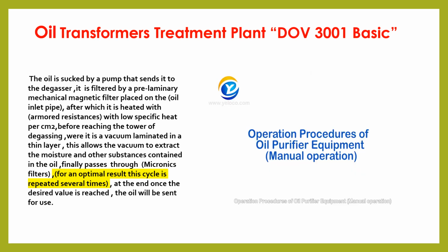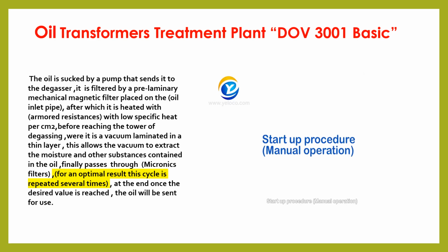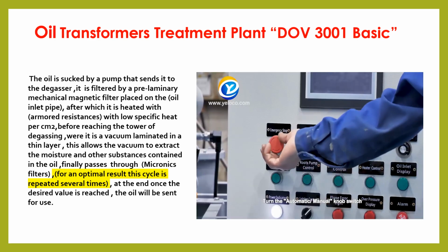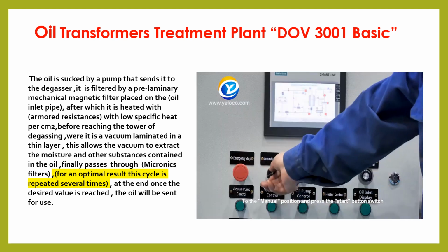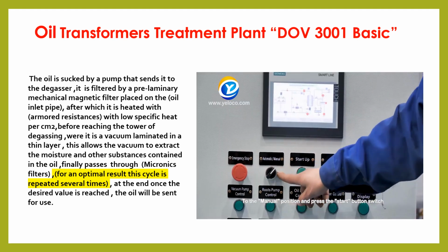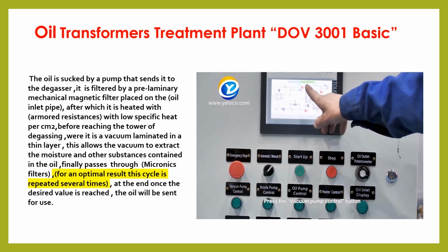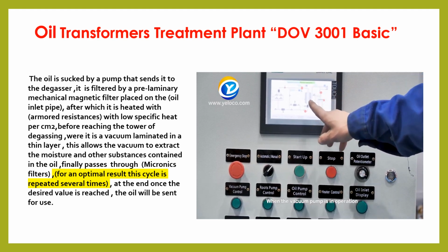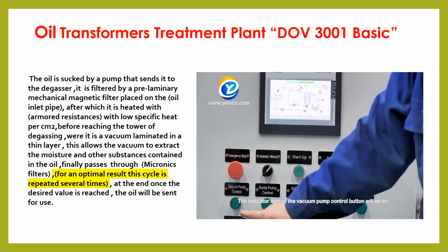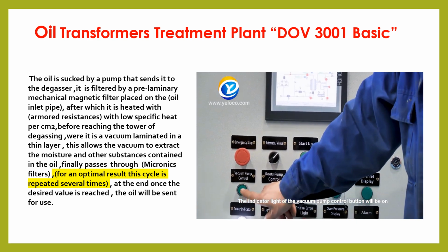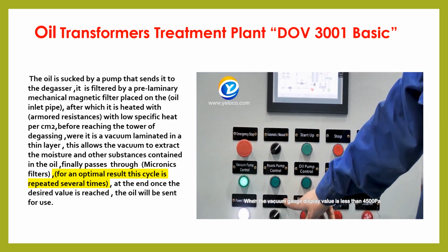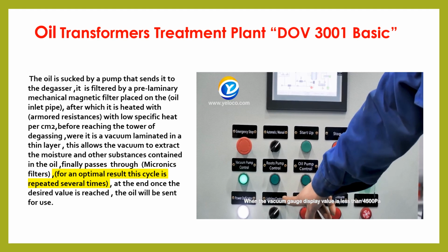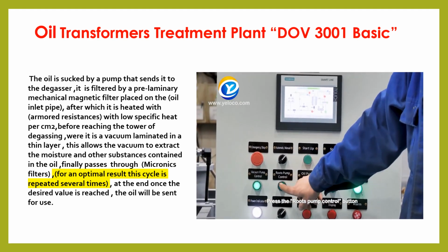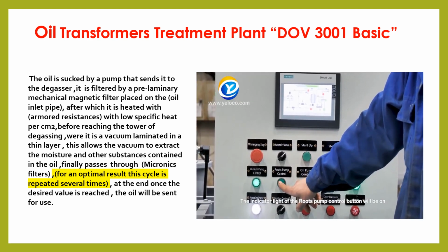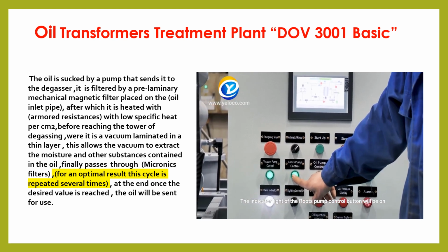Operation procedures of oil purifier equipment, manual operation. Startup procedure, manual operation. Turn the automatic manual knob switch to the manual position and press the start button switch. Press the vacuum pump control button when the vacuum pump is in operation. The indicator light of the vacuum pump control button will be on. When the vacuum gauge display value is less than 4500 Pa, press the Roots pump control button. When the Roots pump works, the indicator light of the Roots pump control button will be on.